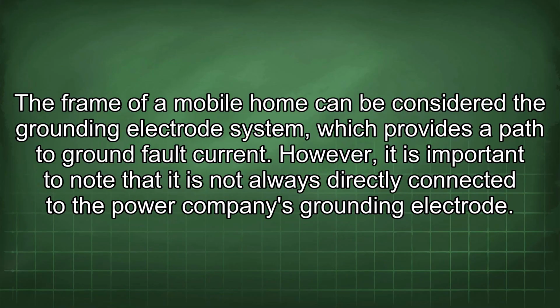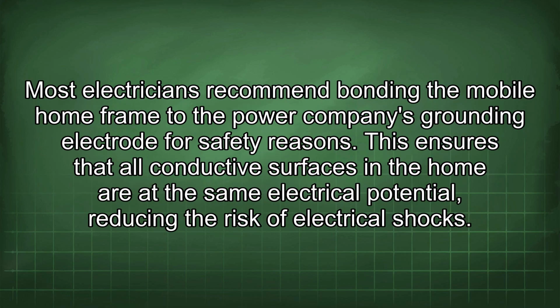Frame of a mobile home can be considered the grounding electrode system, which provides a path to ground fault current. However, it is important to note that it is not always directly connected to the power company's grounding electrode. Most electricians recommend bonding the mobile home frame to the power company's grounding electrode for safety reasons.